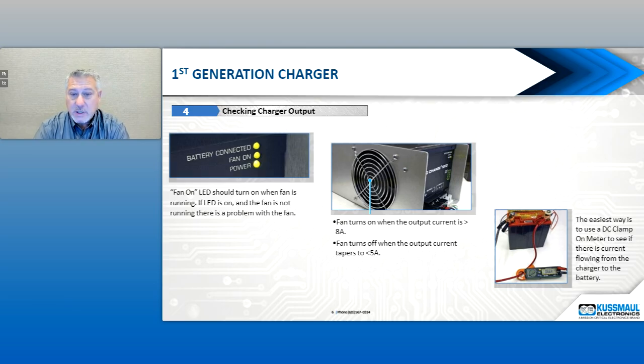and it will turn off when it's approximately 5 amps or less. So if the fan is running, you know current is actually going out of the charger. But just because the fan is not running does not mean there's a problem with the charger. It could be in a float or trickle mode, putting out less than 5 amps, so the fan is not running because the components inside are not getting warm.